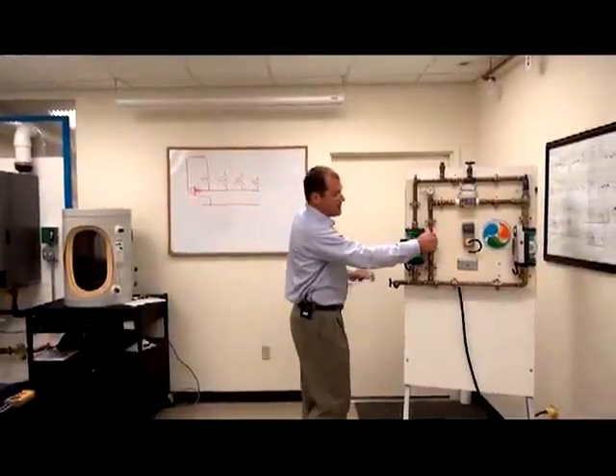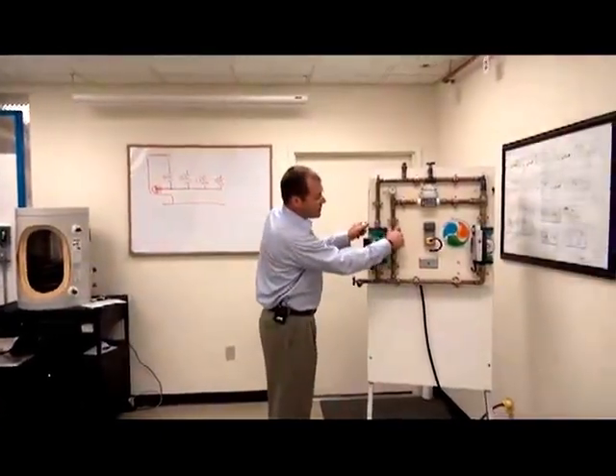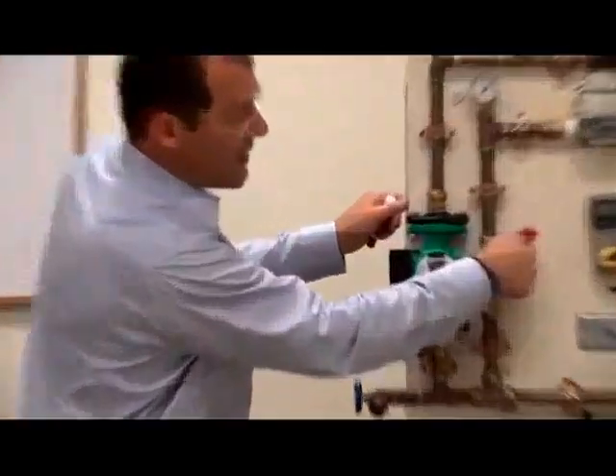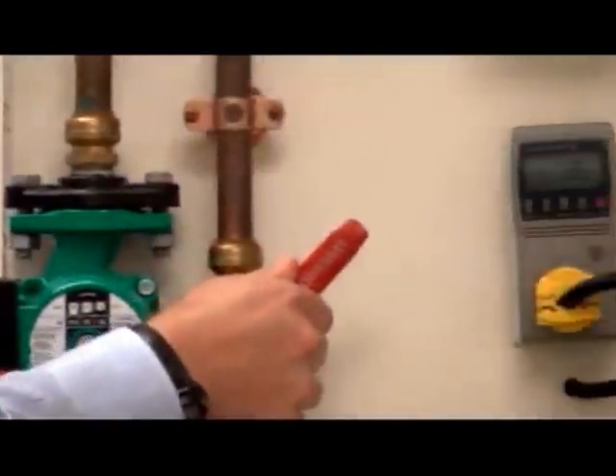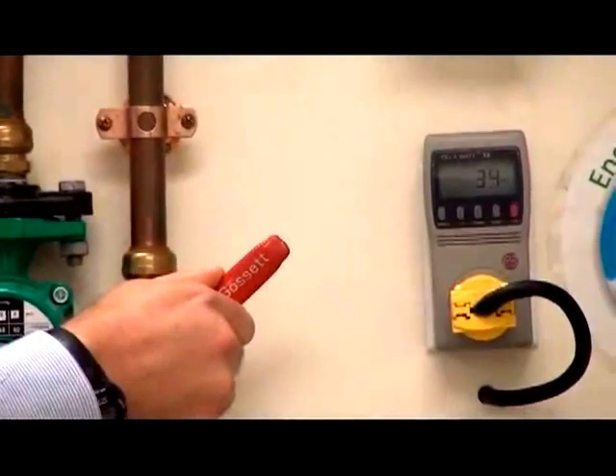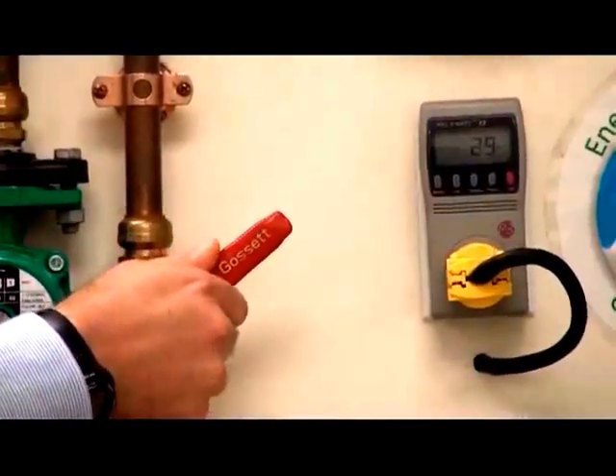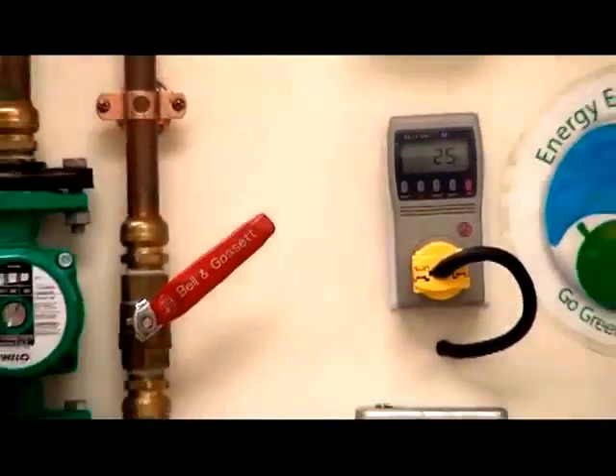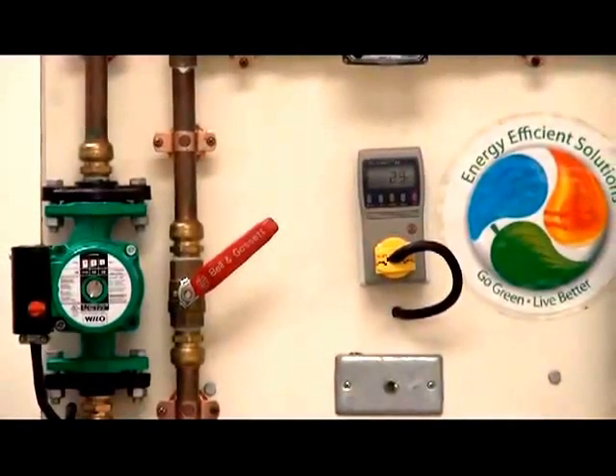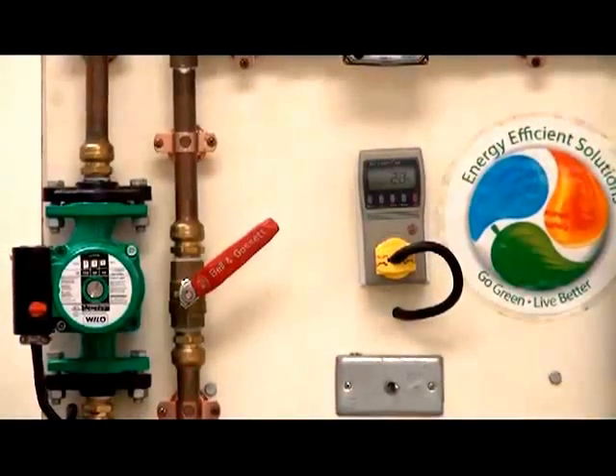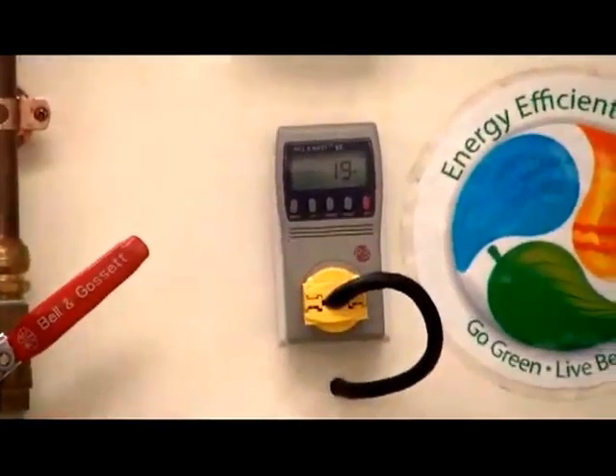So we'll just simulate that. This pump can't do that. But if we close off flow as if two of those valves closed, we drop into the teens in terms of our watt consumption. So most of the year, we're only consuming 15 or 20 watts instead of multiples of 80 watts.